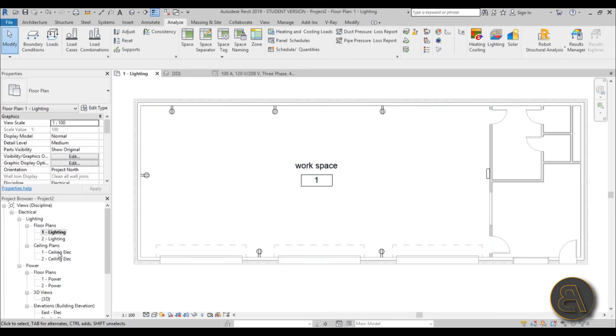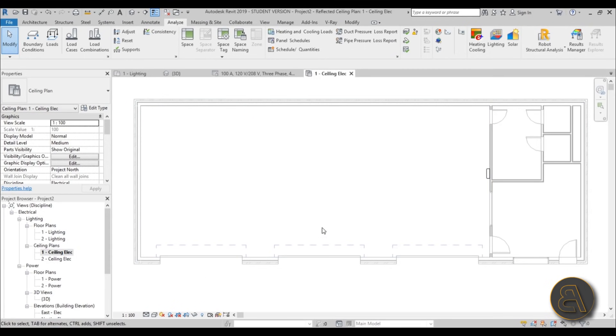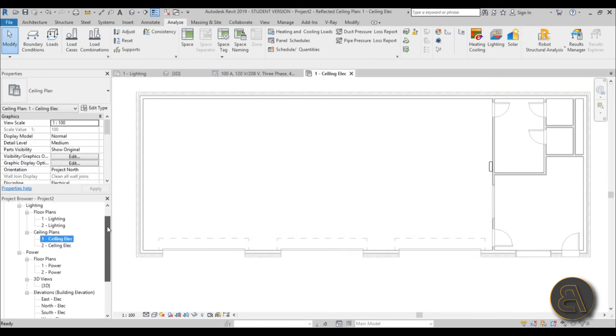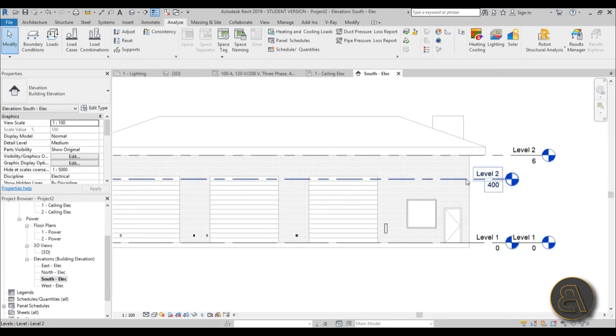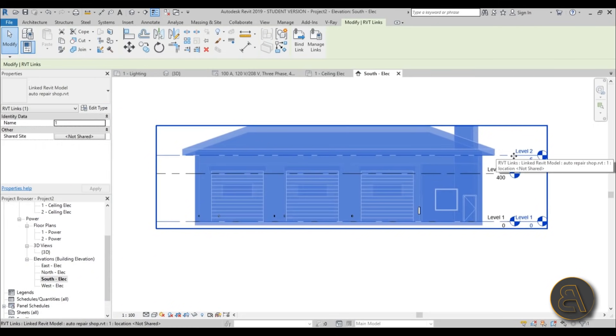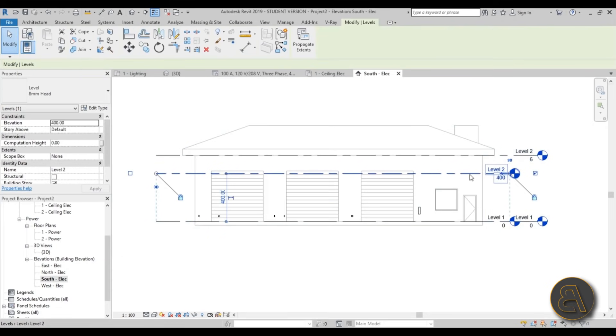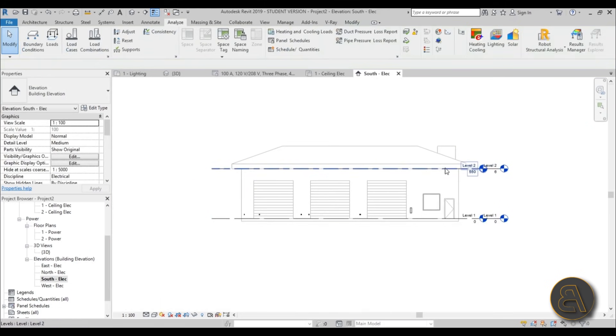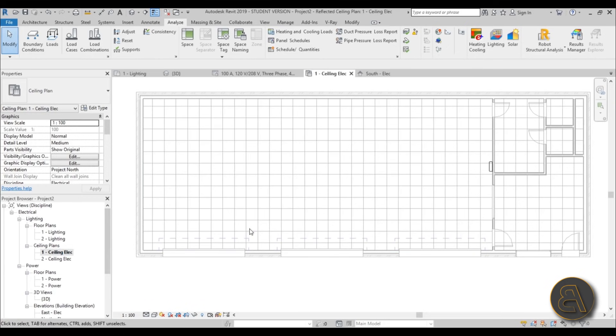Let's light this room up. Go to the ceiling plan. You can't see the ceiling — if you scroll down and go to the south elevation, you can see Level 2 is lower than the level attached to the architecture file. Select Level 2 and move it up to align with the architectural level. Now go back to the ceiling plan and you can see the ceiling. Make sure all levels in the electrical project overlap with the levels in the architectural project.